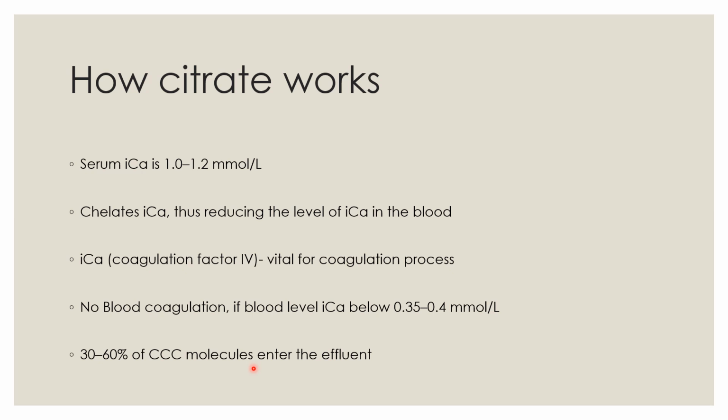As a result, severe hypocalcemia can occur if ongoing supplementation of ionized calcium is not provided. Therefore, an adequate amount of ionized calcium must be supplied directly to the patient intravenously or through the return end of the extracorporeal circulation circuit to maintain physiological ionized calcium level.